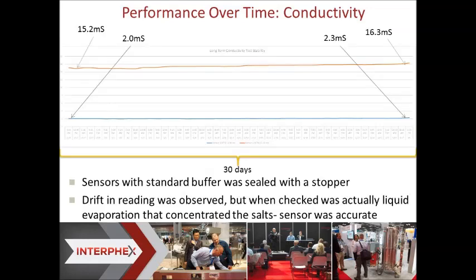We recently did some testing on the conductivity over time. This graph is not meant to be read, it's just meant to point out the key points, which is that this is a 30-day trial. The sensor was filled with standard buffer and sealed with a stopper. At the beginning of the 30 days, it read 15.2 on one and 2.0 on the other, so we had two different buffers. You see over time it did drift up. But when we looked back at the actual sensor and the buffer that was used, there was some slight evaporation of liquid, which caused the salt concentration to rise. So it was determined over time that the sensor did not have any drift within itself.